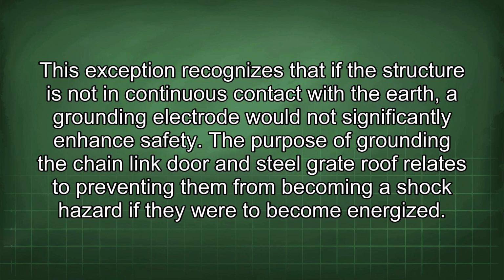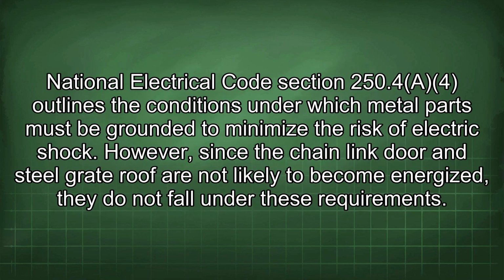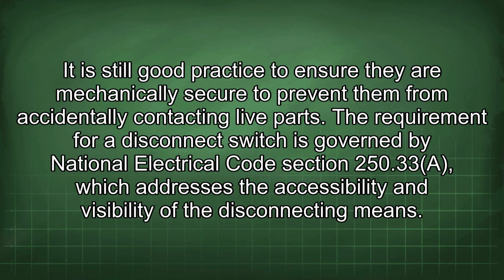The purpose of grounding the chain-link door and steel grate roof relates to preventing them from becoming a shock hazard if they were to become energized. National Electrical Code Section 250.4 outlines the conditions under which metal parts must be grounded to minimize the risk of electric shock. However, since the chain-link door and steel grate roof are not likely to become energized, they do not fall under these requirements.